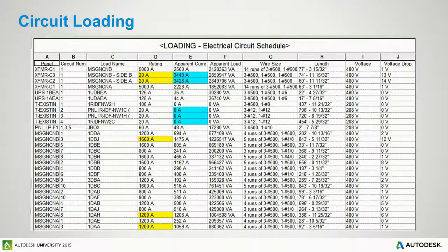Revit refuses to size a breaker. Absolutely refuses. They are not going to make any attempt to size a breaker. It gets into legal ramifications and such, and they're like, I want no part of that. So Revit defaults to 20 amps. Just across the board, no matter what it is, Revit will always put in 20 amps for the circuit, for the breaker size.